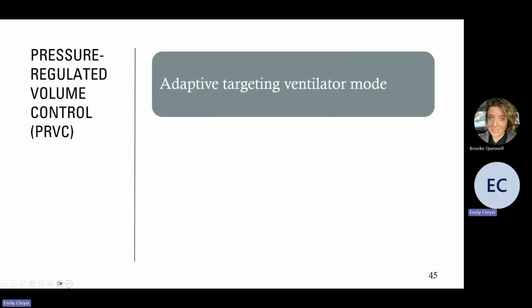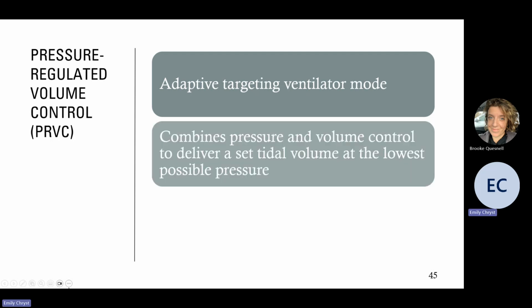The next mode is a bit newer, and a lot of people are pretty excited about it. Your ventilator is capable of this mode. It's called pressure regulated volume control. So this is an adaptive targeting ventilator mode, which basically just means that these smart ventilators are going to analyze every breath they give and deliver the next breath based on what they learned from the patient in the previous breath. So it's attempting to create sort of the best of both worlds with pressure control and volume control. So it's analyzing those pulmonary dynamics breath by breath to continuously make adjustments.